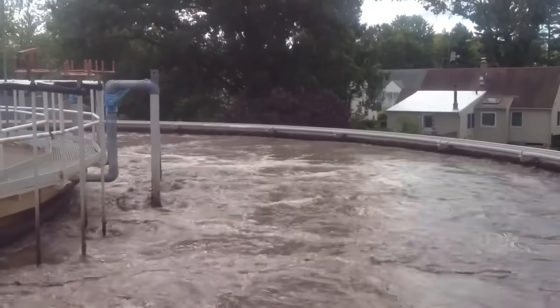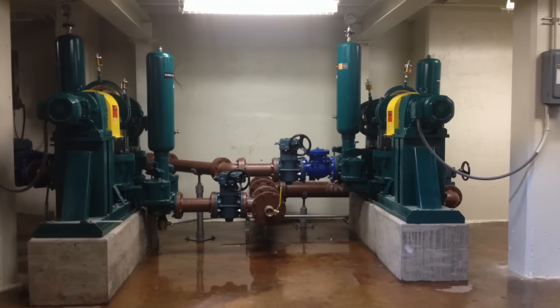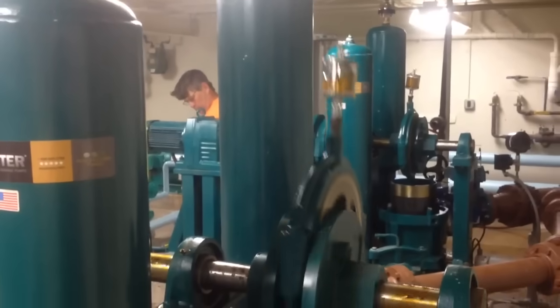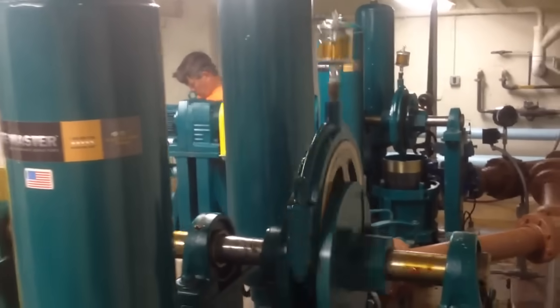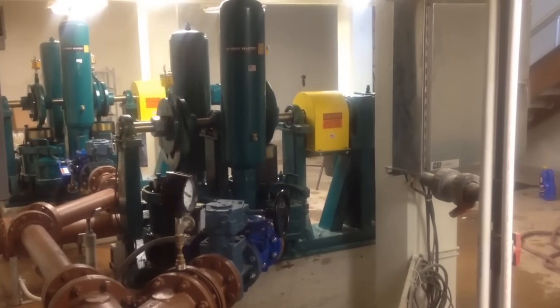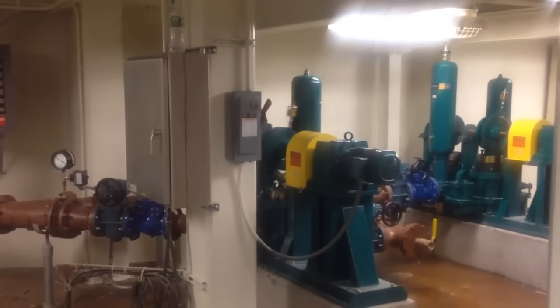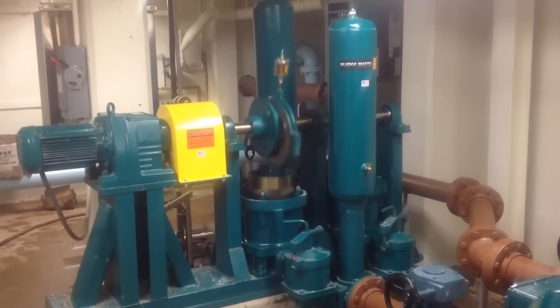and other solids-laden liquids. Wastecorp recommended that the facility go with two Sludge Master PE942 plunger pumps to transfer up to 10% solids. Each pump is rated for up to 170 gallons per minute of solids-laden wastewater. These sludge pumps are equipped with the latest energy-saving motor systems and are connected to a variable frequency drive system to control driver speed. With next-generation gearboxes, these plunger pumps optimize productivity while conserving energy.